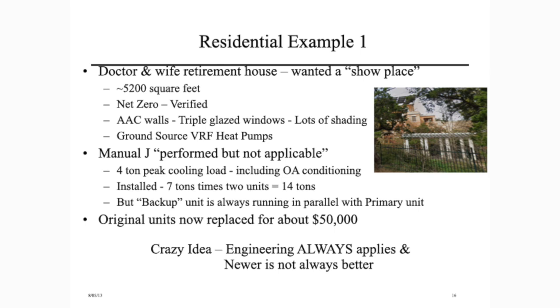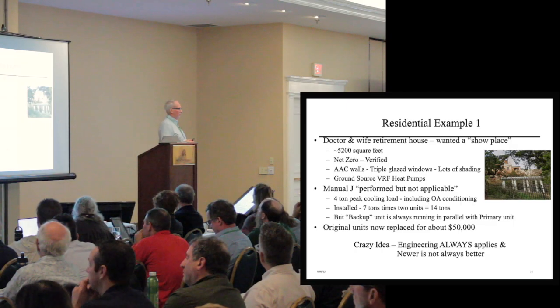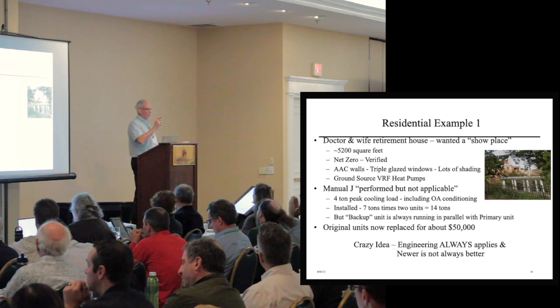Let me point out, they wanted the latest, the greatest, the best. They went with ground source VRF heat pumps. I wrote them an email and said, I really don't recommend that. This was early days of ground source VRF. And what I told them was, I think the systems are great. I think they have huge potential. But can you get somebody to service it?